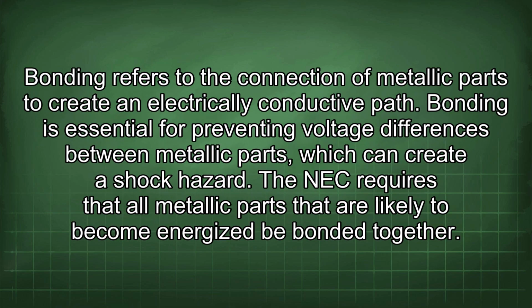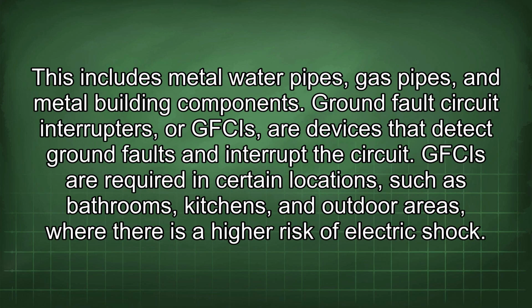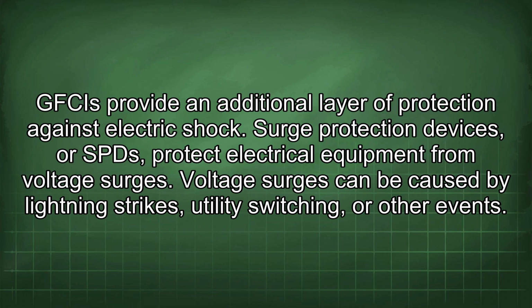The equipment grounding conductor must be properly sized and installed to ensure that it can safely carry the fault current. Bonding refers to the connection of metallic parts to create an electrically conductive path. Bonding is essential for preventing voltage differences between metallic parts, which can create a shock hazard. The NEC requires that all metallic parts that are likely to become energized be bonded together. This includes metal water pipes, gas pipes, and metal building components. Ground fault circuit interrupters, or GFCIs, are devices that detect ground faults and interrupt the circuit. GFCIs are required in certain locations such as bathrooms, kitchens, and outdoor areas, where there is a higher risk of electric shock. GFCIs provide an additional layer of protection against electric shock.